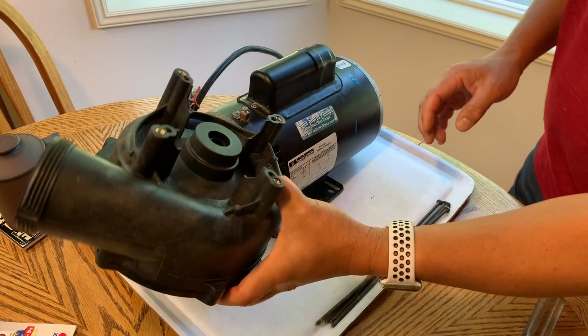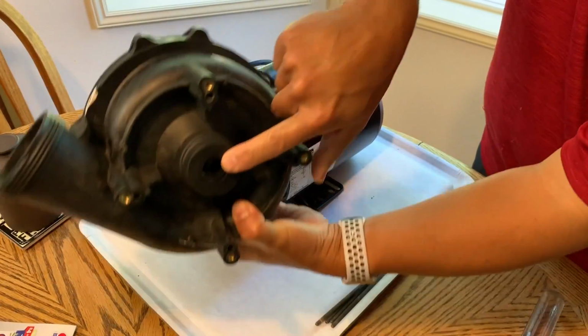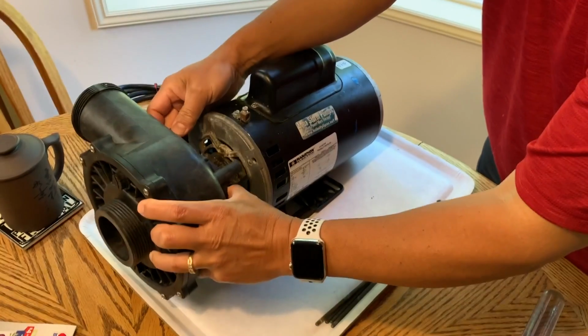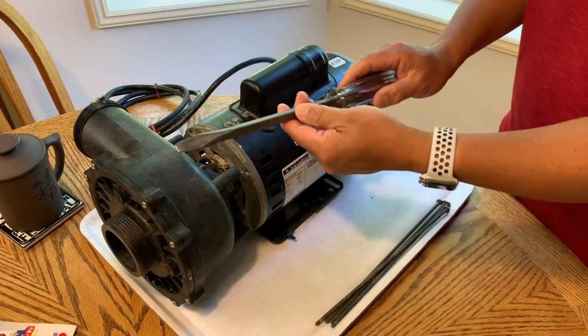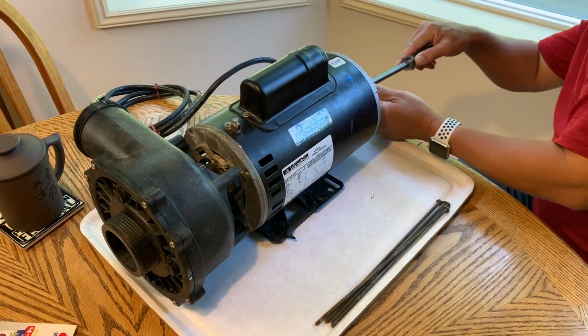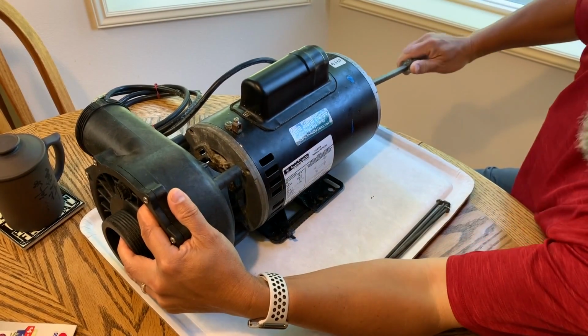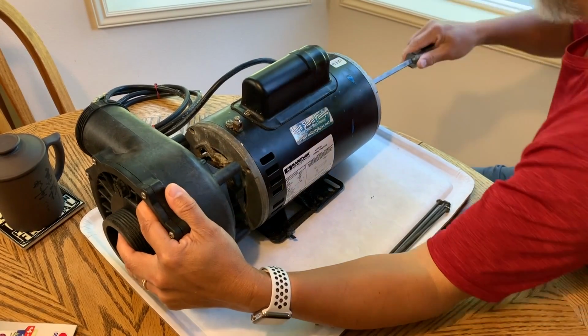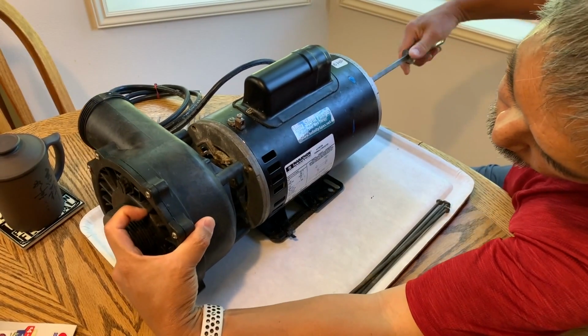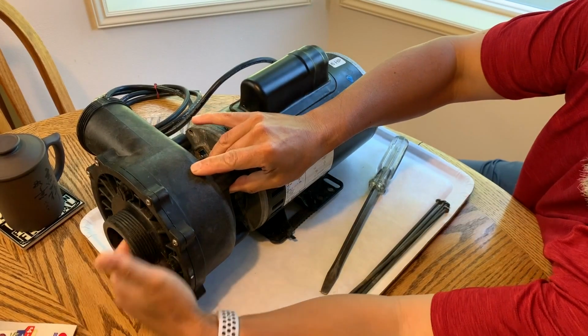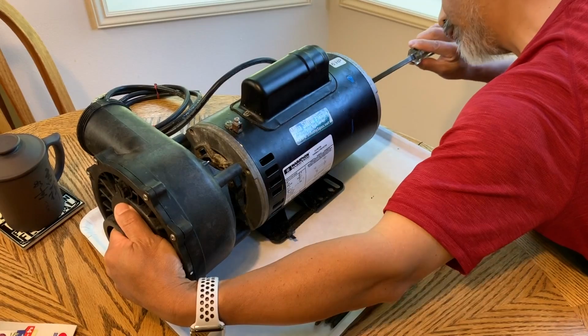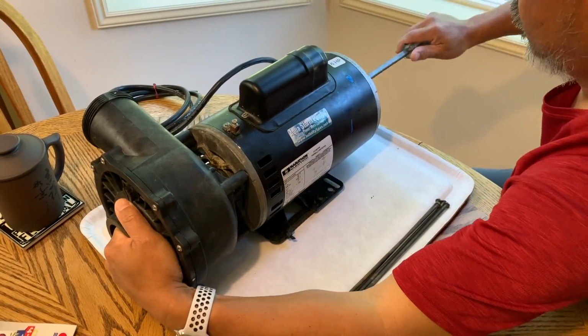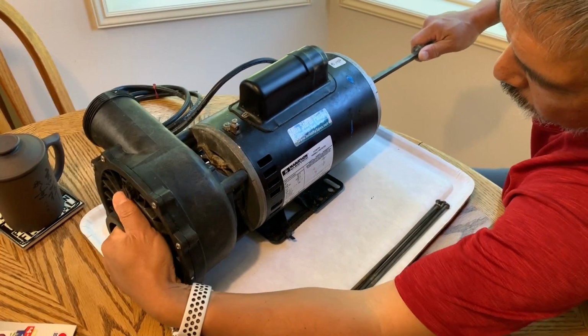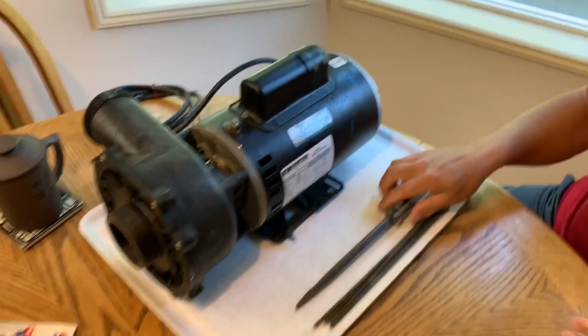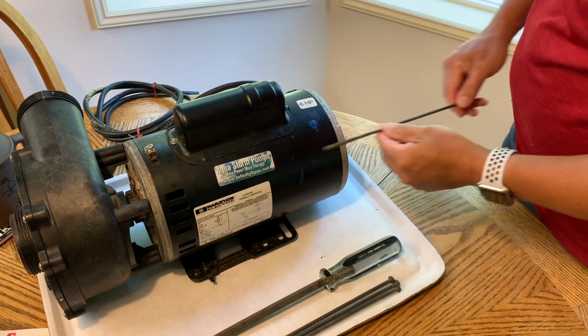We should be able to attach this new wet end to the motor simply by threading this back over the shaft. We're going to use a flat screwdriver, insert it in the end of the shaft here, and turn the shaft. I'm turning the shaft clockwise. And I'm going to reach inside with my finger here and just hold the impeller to keep it from rotating as I turn. And that feels like it's getting tight now. We'll reinsert these long bolts that run through the motor here. Line those up with these legs.